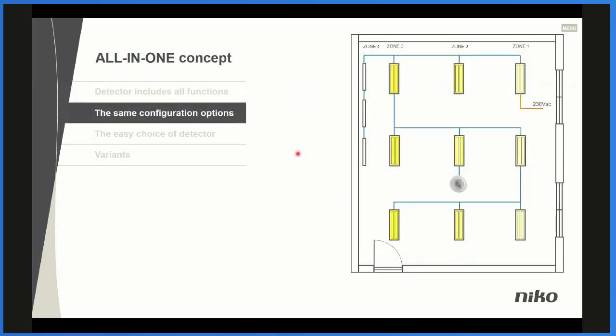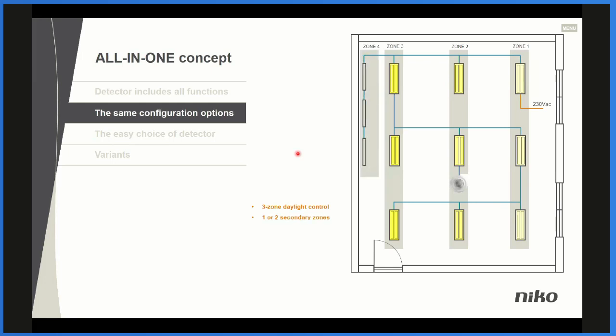If you want to have the same configuration, you have the options to do that. You can build it as 3 zones of daylight control, or it could be 1 or 2 secondary zones. If you have 2 daylight zones, you have up to 2 secondary zones. There's a total of 4 zones, and how you divide them is nearly up to you. In order to decide that, we always need two zones for daylight control.